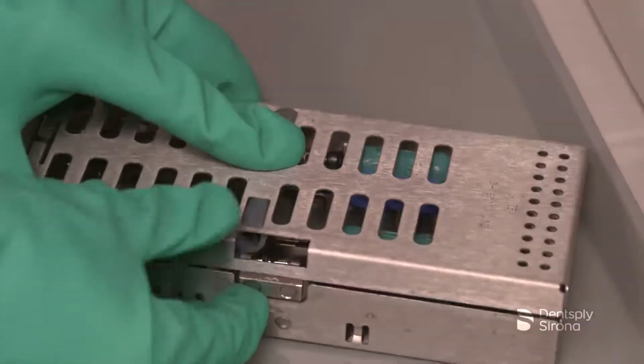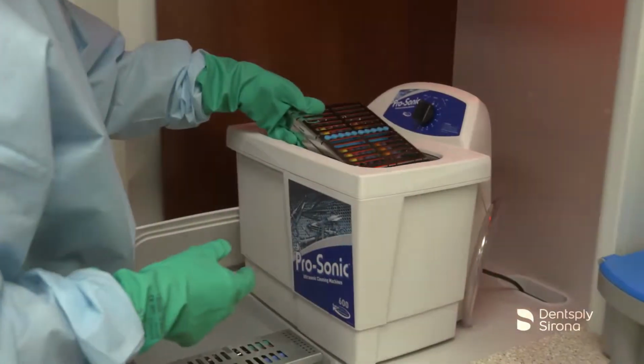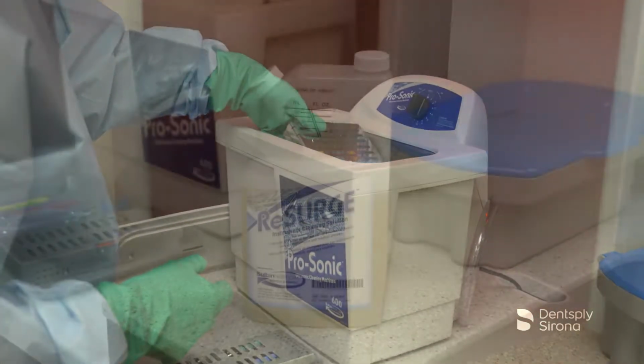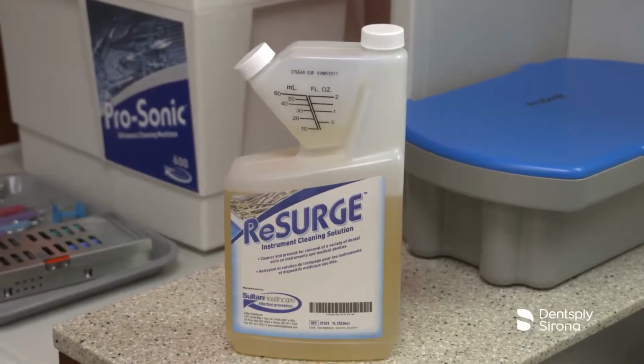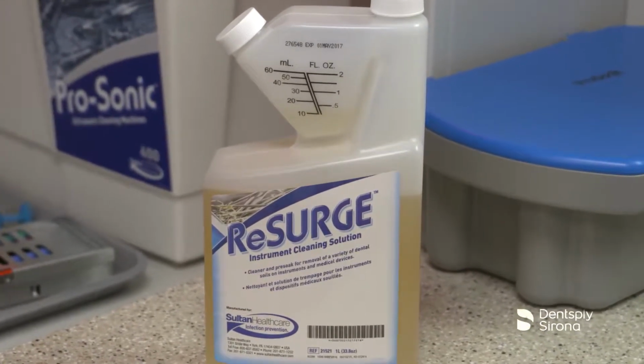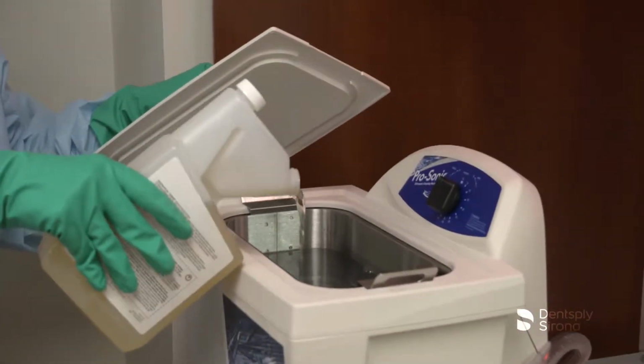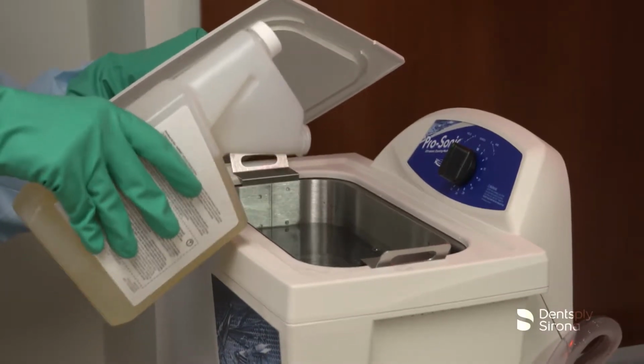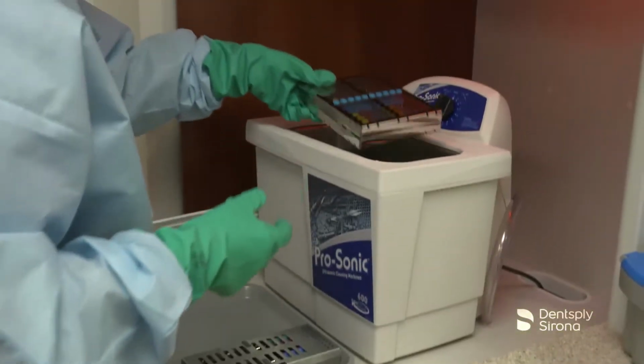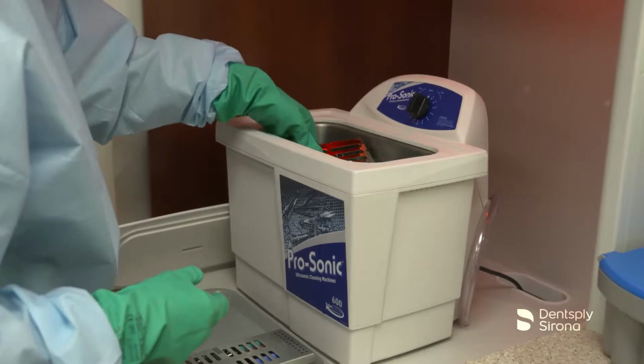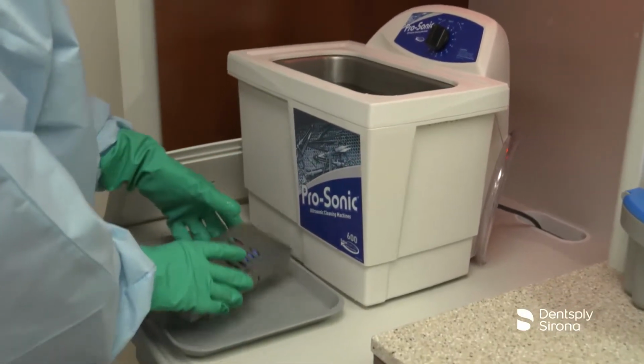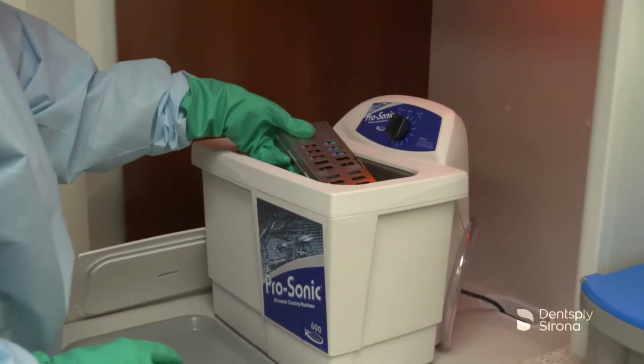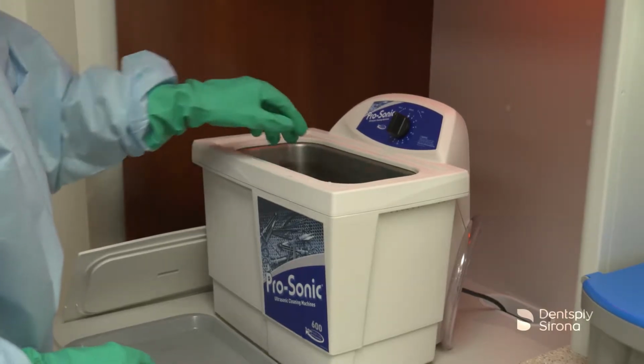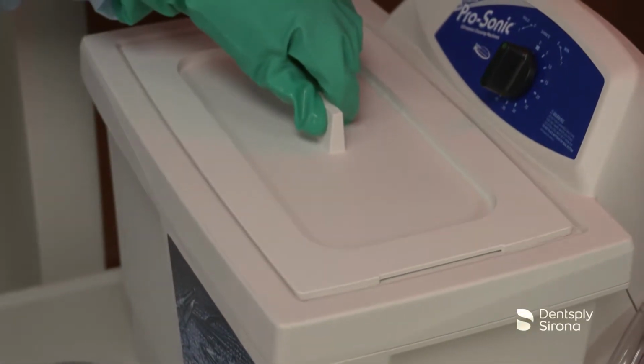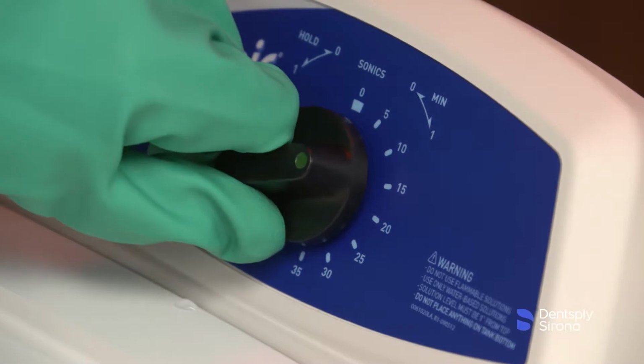Cavitron ultrasonic inserts may be cleaned using an ultrasonic water bath for up to 15 minutes. A pH-neutral instrument cleaning solution, such as Resurge, is recommended for ultrasonic cleaning with Cavitron inserts for up to 15 minutes. It is important to adhere to the ultrasonic cleaning bath manufacturer's recommended liquid level. Place the device into the ultrasonic bath and ensure that the instruments are sufficiently covered. Place the cover and set the unit for the indicated contact time.